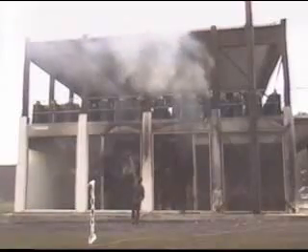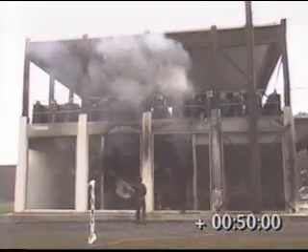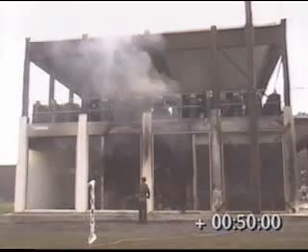At 20 minutes, the fire was burning at a very low level. After a further 20 minutes, a piece of timber was thrown through the window of the small office, resulting in a small hole, but no significant fire growth. After about 50 minutes, the windows of the small office were smashed, but again this did not result in any increase in fire size. Approximately 6 minutes later, fires were started at 4 places in the open plan area. Eventually, the fire in the open plan area began to grow due to the ventilation created by the smashed windows.